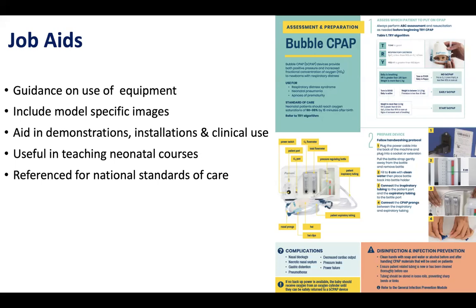As you can see from the image on the screen, there are images and very few words. So they are quick reference, they are easy to use, and people can use them in the clinical setting very easily. That is certainly what is happening within the countries. However, they are also useful from an education point of view, both within pre and in-service training. We have used these within Malawi in training our medical students on the equipment, and we've used them in a process called speed dating, where they rotate through the equipment and have a brief period of time with the equipment, and we make reference to the CPAP job aids as we do it.